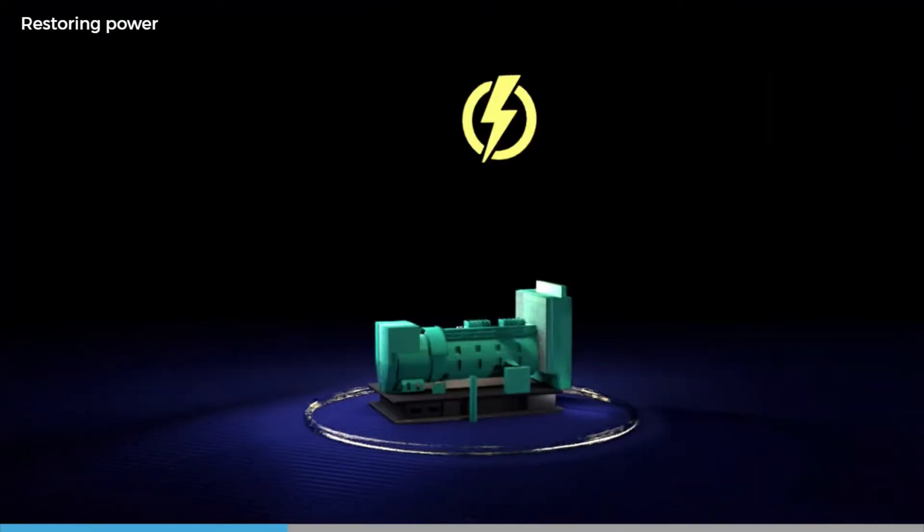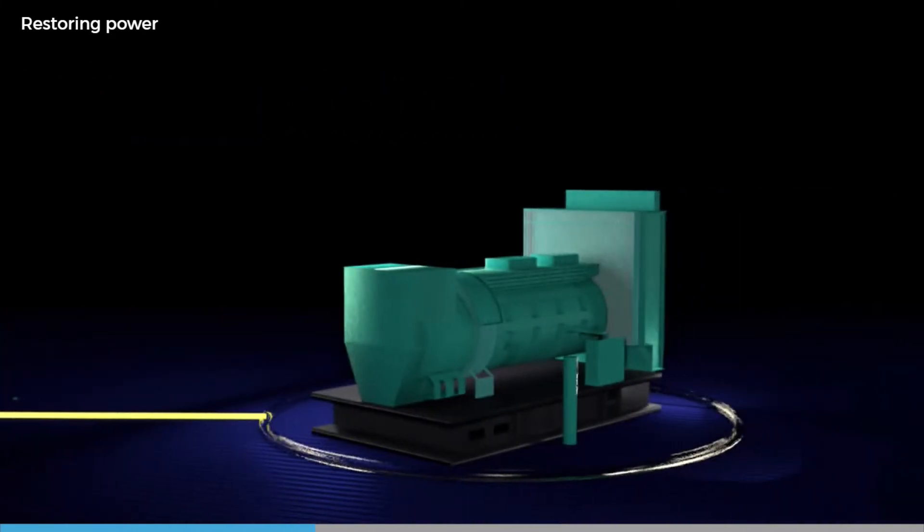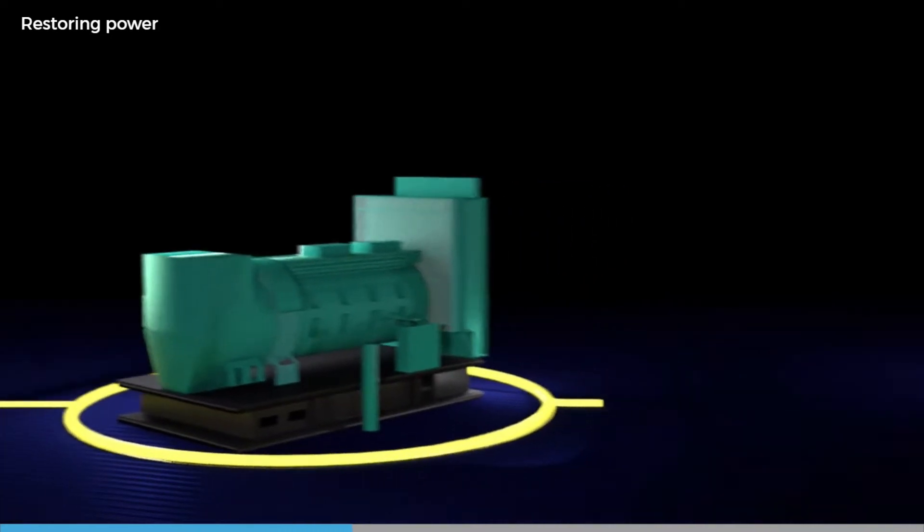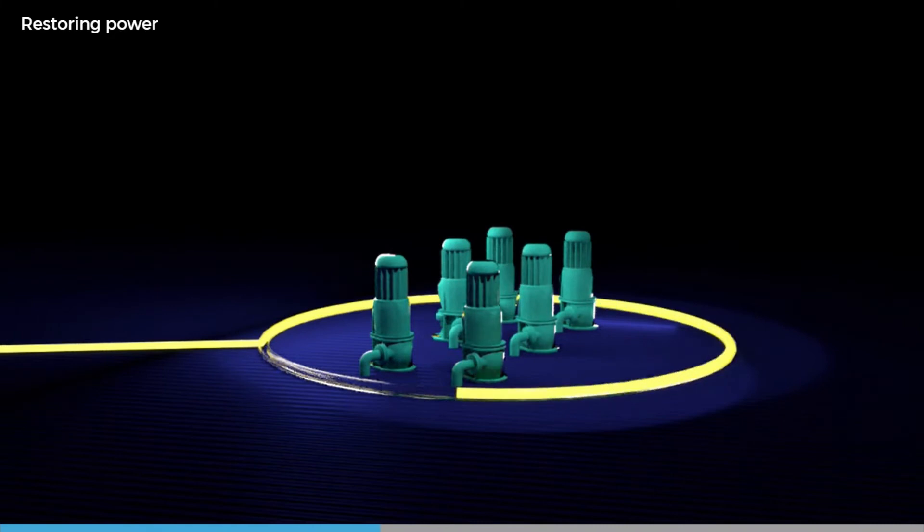The emergency generator might give you all the power you need to start a main generator. But then you might only have a limited amount of time to start seawater and freshwater pumps, necessary to provide cooling for this main generator.